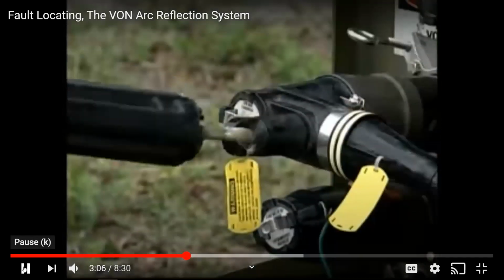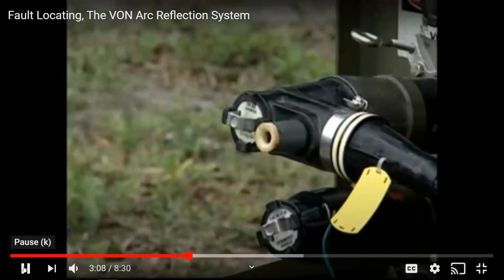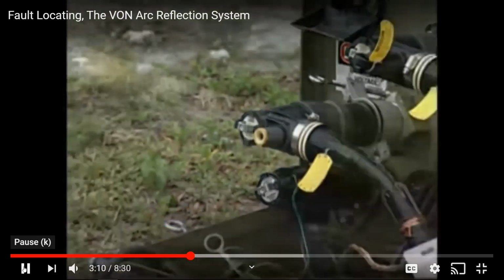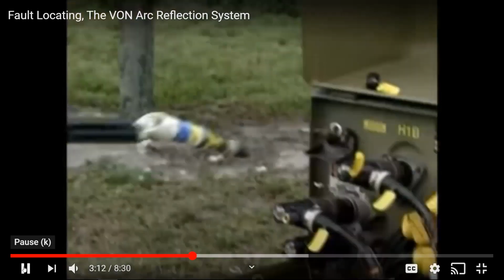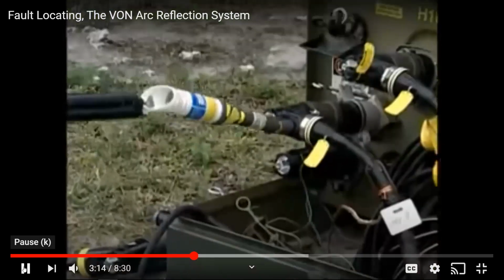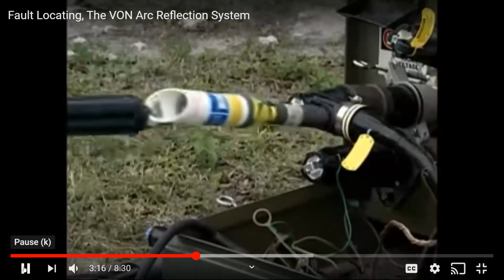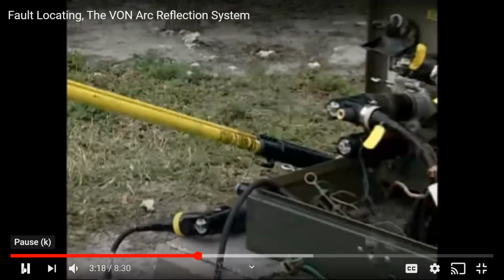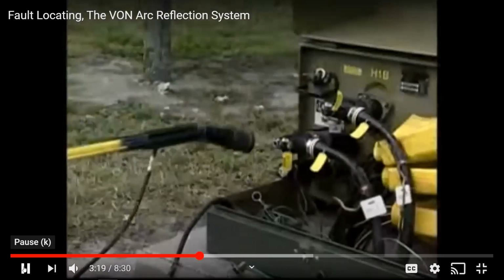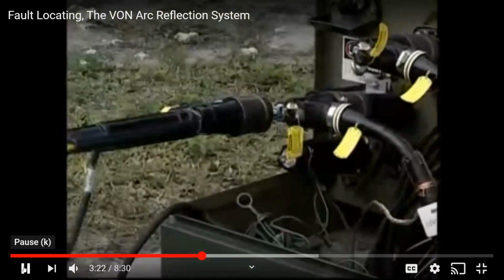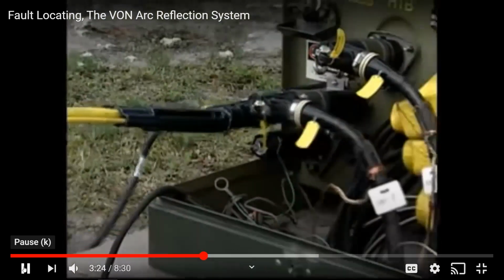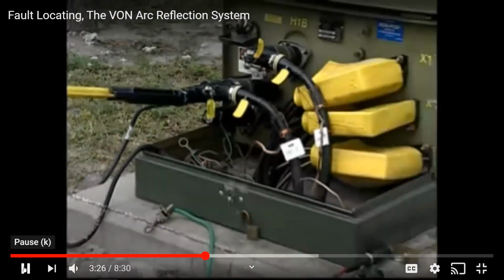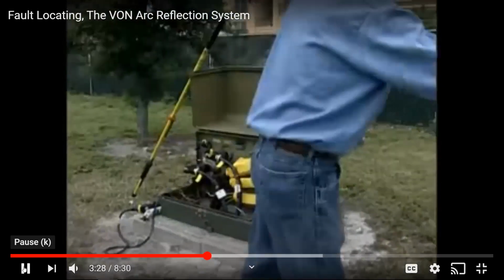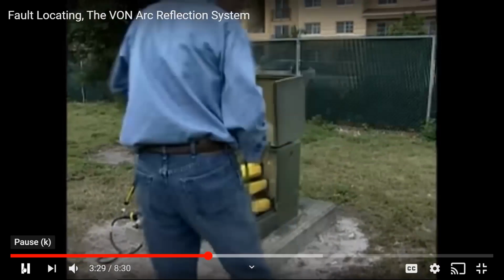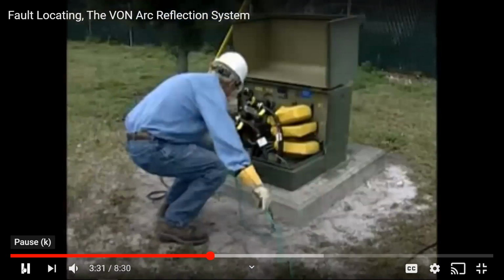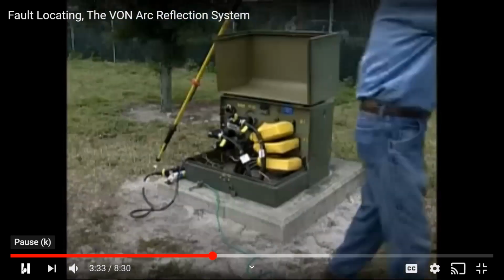Some utilities test from the parking bushing by removing the access port cap. Then, using an approved voltage meter or detection device, test the other side of the feed-through or test port to ensure the cable is de-energized. After you complete the testing, be sure to insert a grounding elbow in the feed-through. You're now ready to hook up the leads from the VON. One quick note, be sure the green safety case ground is uncoiled fully before beginning the hookup.